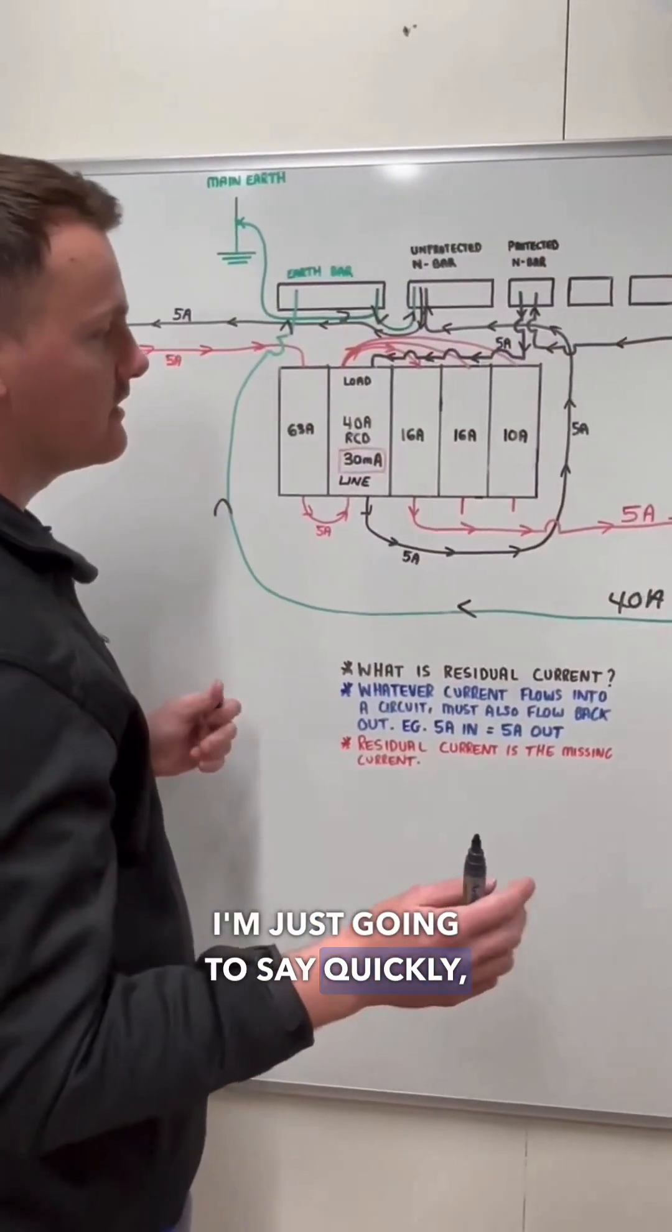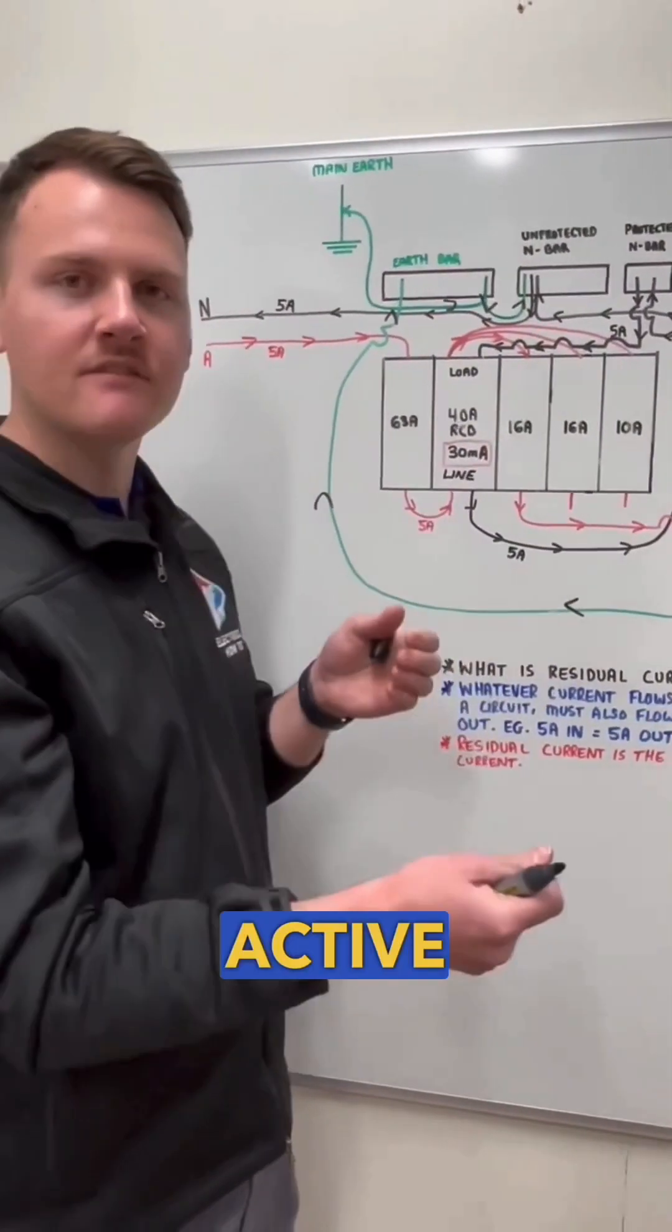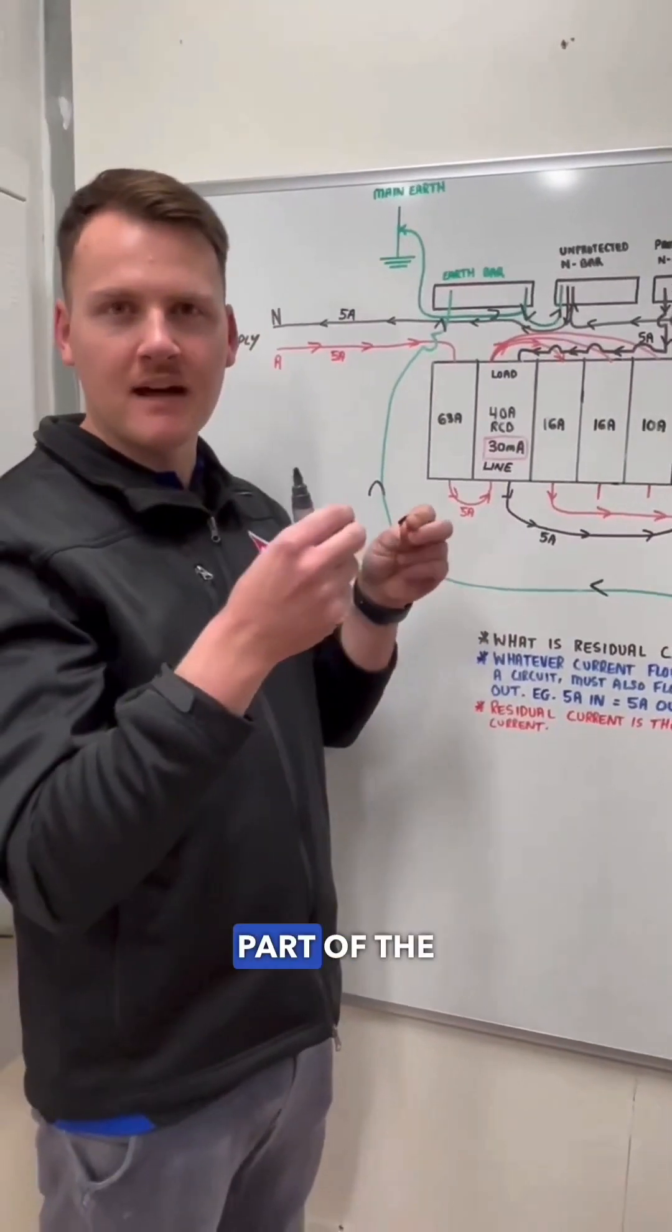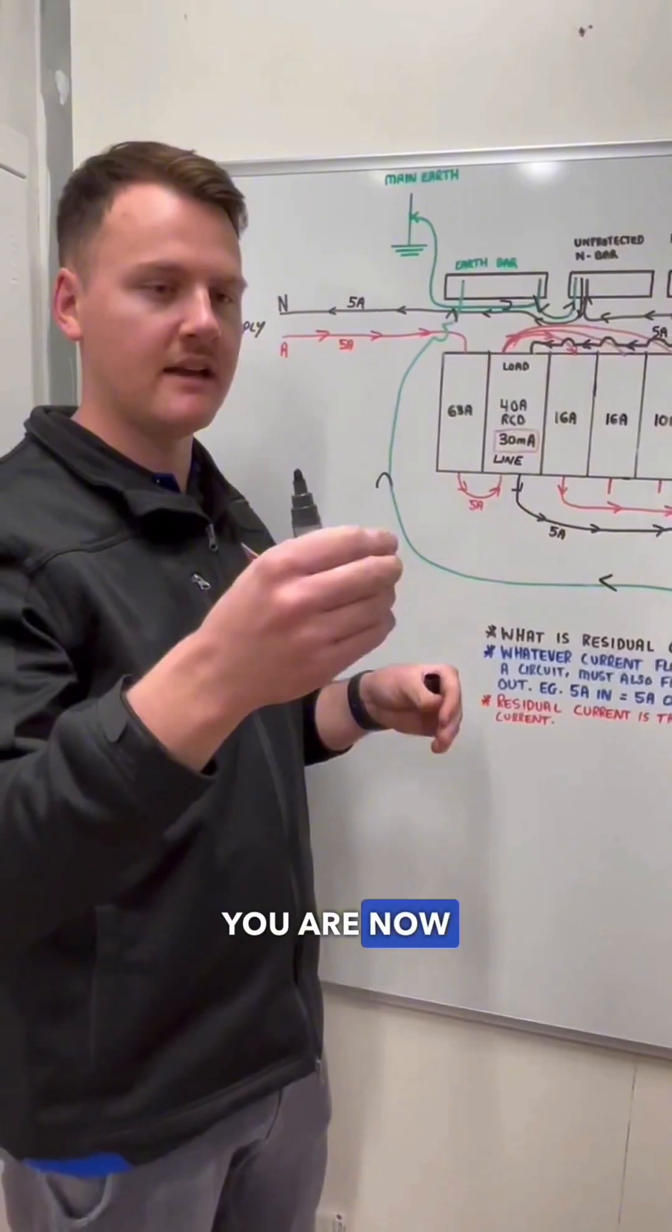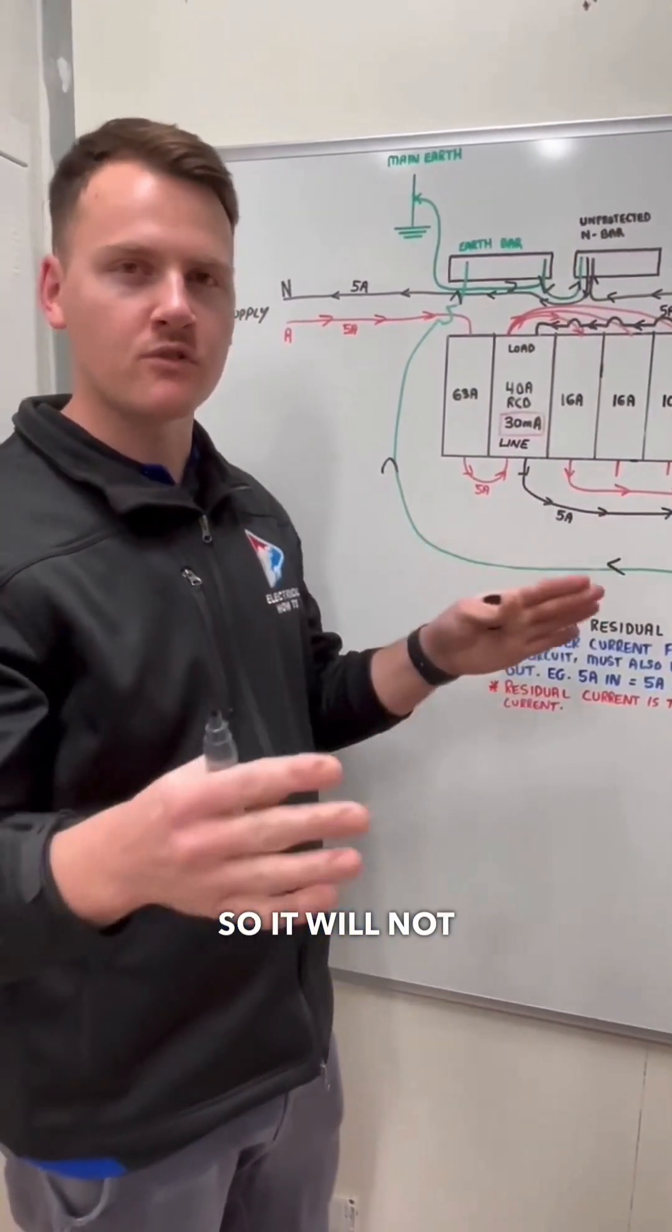Now, I'm just going to say quickly, if you were to just grab the active and neutral, you actually just become part of the circuit. The safety switch isn't going to trip. There's no imbalance of current. You are now the active and you're returning through the neutral. So it will not trip.